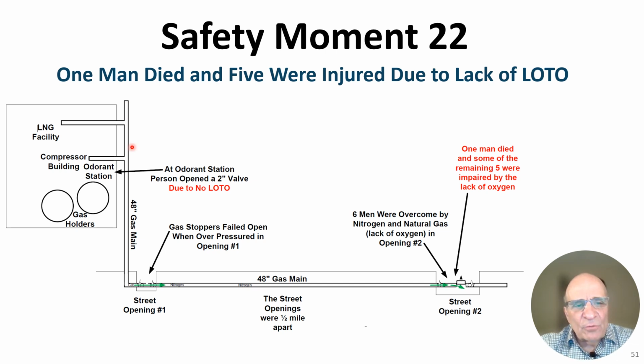What was happening at that time, this was a 48-inch gas main, and it went from a place where there was a stopper installed. This 48-inch gas main went for quite a long distance, many blocks, to another location. There was no stopper installed, and this entire line was filled with nitrogen. Men were working here to remove a section of pipe. And there was another stopper here as well. Because of the failure to lock out and tag out a 2-inch valve at the odorant station, the operator came out of the compressor building, saw that the valve that was normally open was closed, and he opened that 2-inch valve. That overpressurized the stoppers, blew the stoppers, and just at the time the crew here was removing this section of 48-inch pipe, this pressure came down, blew this stopper here, and that nitrogen started flowing into the opening.